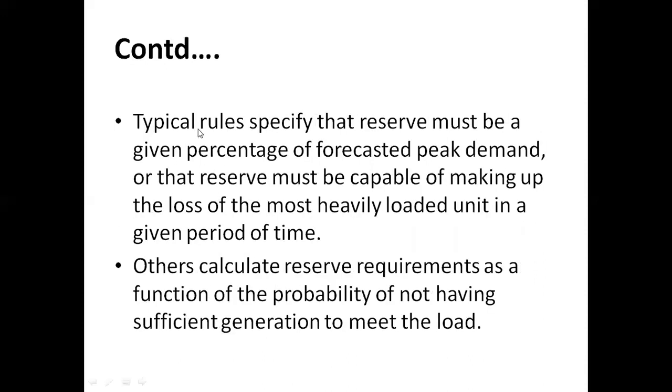So typical rules specify that reserve must be a given percentage of forecasted peak demand. That reserve must be capable of making up the loss of the most heavily loaded unit in a given period of time. So it is clear that generally the rules concern the load pattern or the load characteristics that we have.